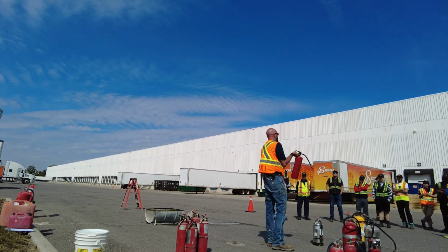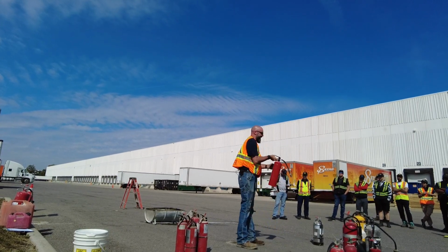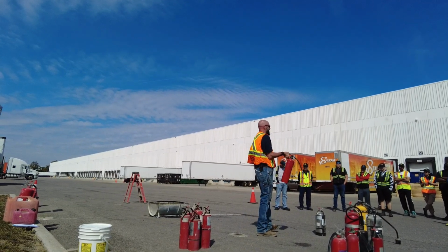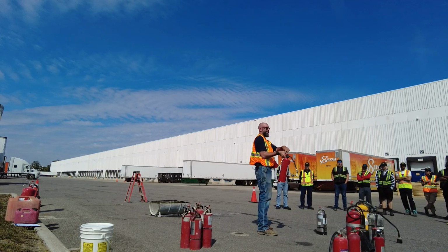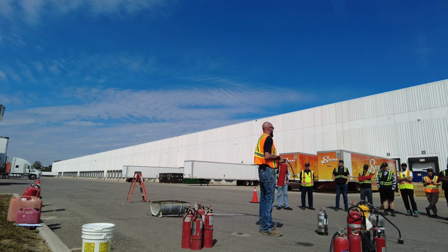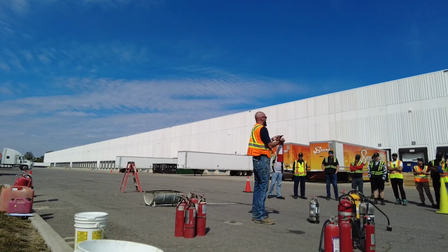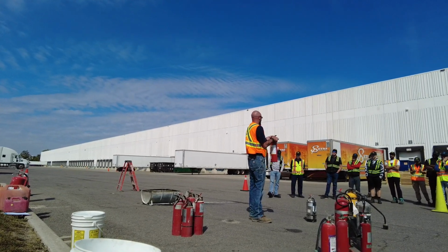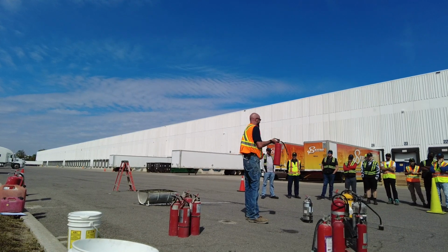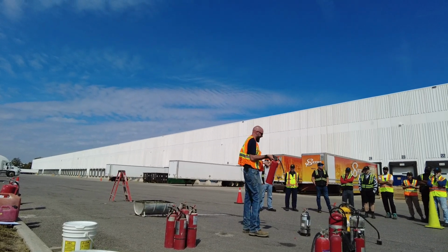This is called the carry handle. Grab it by just the bottom handle. The reason I point this out, when you come up, you'll notice the pull pin that stops it from going off goes right through to the other side. If I put my hand on here, I'm literally fighting against myself to pull this out. In moments of panic, I've had customers squeeze the handles together and lodge the pin in there so it has to be replaced. If they just grabbed it by here, finger in, twist and pull, it slides right out.